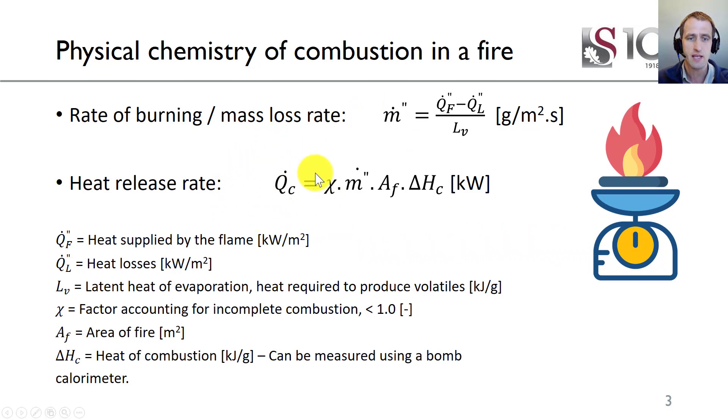Our total heat release rate is some factor accounting for incomplete combustion—let's say 0.9, 0.95, or 0.8 depending on the material. We know our calorific value from a bomb calorimeter, the area of fire, and our mass loss rate. So from a mass loss, we can get to a heat release rate for a heptane fire or polyurethane or something as a single material.